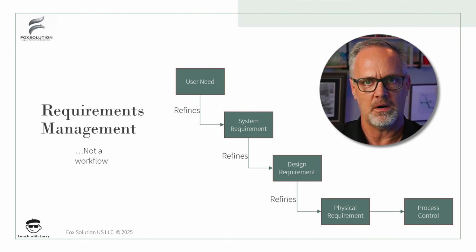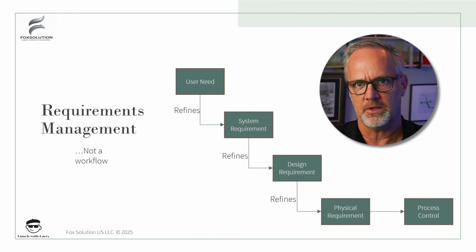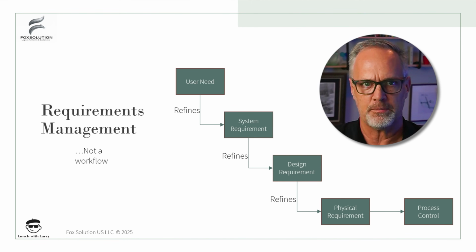This is more, how do we explain what the inputs to the design are so that eventually when we get completed with the design, we'll be able to explain how the device works and then show that traceability to our evidence. So that's really what this is all about. It's not a workflow, it's really a decomposition, a logical decomposition model.